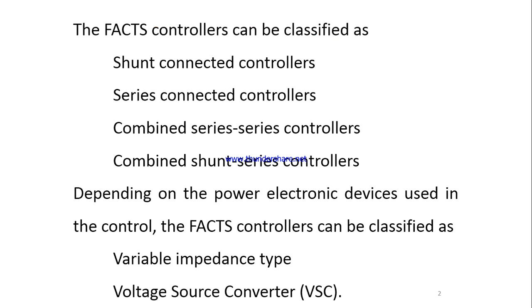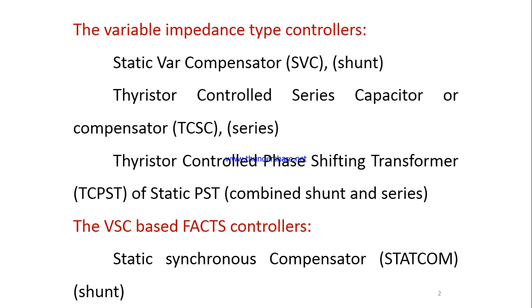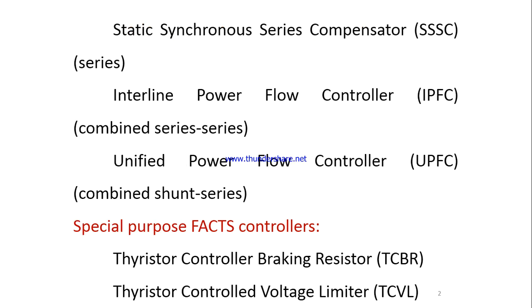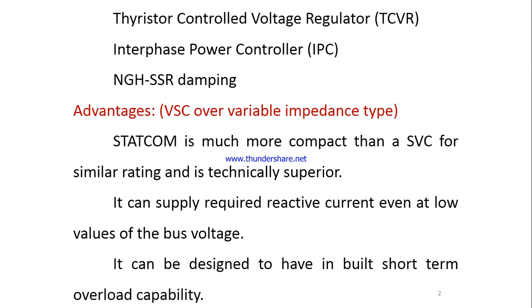We can see the different types: shunt controllers, series controllers, combined series-series, and combined shunt-series. Depending on the power electronic devices used in the controller, FACTS controllers can be classified as variable impedance type and voltage source converter type. The variable impedance type controllers are the static VAR compensator or SVC, the thyristor controlled series capacitor or compensator, the thyristor controlled phase shifting transformer or static PST, and the combined type, which combines shunt and series. The VSC based FACTS controllers are the static synchronous compensator, STATCOM, the static synchronous series compensator, the interline power flow controller, the unified power flow controller, etc. Special purpose FACTS controllers are the thyristor controlled braking resistor, thyristor controlled voltage limiter, thyristor controlled voltage regulator, interphase power controller, NGH SSR damping, etc.